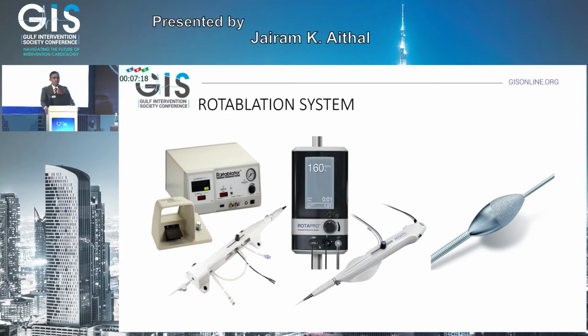So what does the rotablation system look like? The old rotablator had the console, had a foot pedal, had the advancer and the rota burr. The rota burr came in various sizes, starting from 1.25 to 2.5. And we'd use it on roughly a 0.5 burr to vessel ratio. The new Rota Pro is something that can be handled with just one operator, which makes it far easier, far more handleable, and at least the results are dependent only on your own hands, rather than you've got less people to blame. So that's the Rota Pro there.